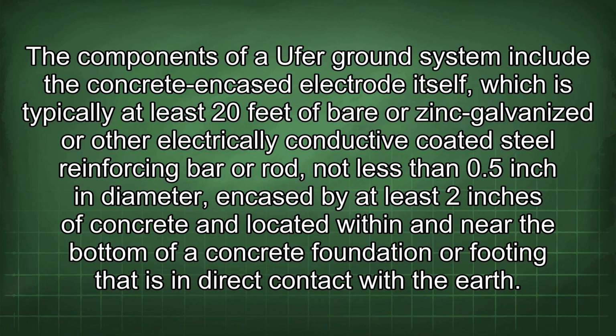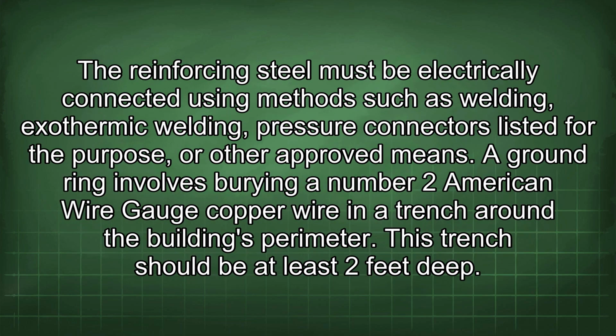at least 20 feet of bare zinc galvanized or other electrically conductive coated steel reinforcing bar or rod, not less than 0.5 inch in diameter, encased by at least 2 inches of concrete and located within and near the bottom of a concrete foundation or footing that is in direct contact with the earth.